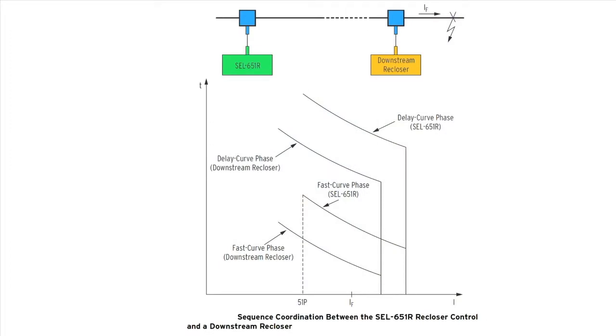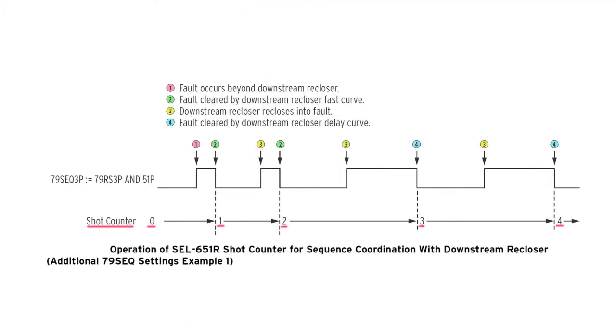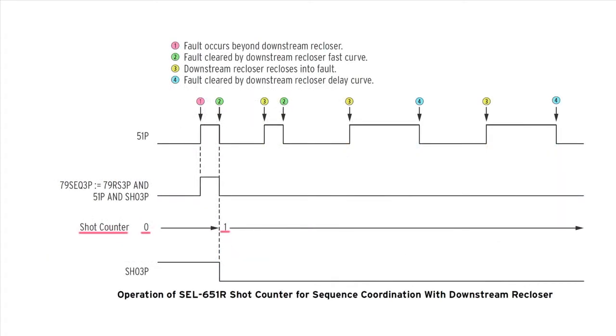The 651R control coordinates the sequencing between the controller and the downstream recloser. Fast and slow time curves are applied appropriately. This figure shows the sequence of timed events as the 651R goes through its normal 4-shot program to final lockout. The status LEDs on the front panel indicate the state of the action sequence. This figure shows the sequence of a fault that is immediately cleared.